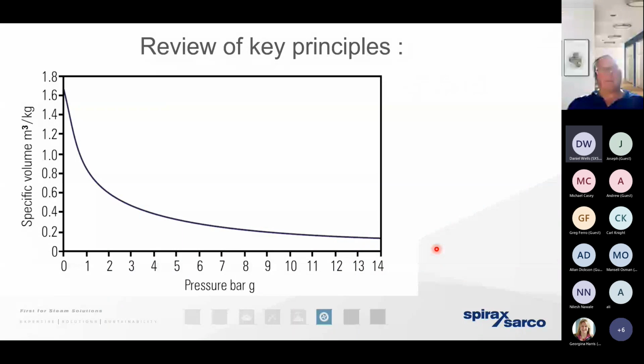A kilogram of water going into the boiler. It's a non-compressible fluid, so it's going to have a volume of 1 litre or 0.001 cubic meters. And as it changes state to produce steam as a gas, it's expanded so that that same kilogram has now got a volume of 1.673 cubic meters. It's expanded to a factor of about 1,673 times. But in reality, our client's going to be generating steam under pressure, 10 bar gauge. And we remember the benefit of generating steam at that pressure where we can reduce its volume.